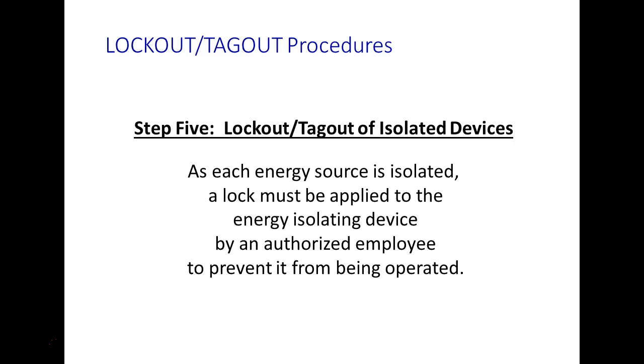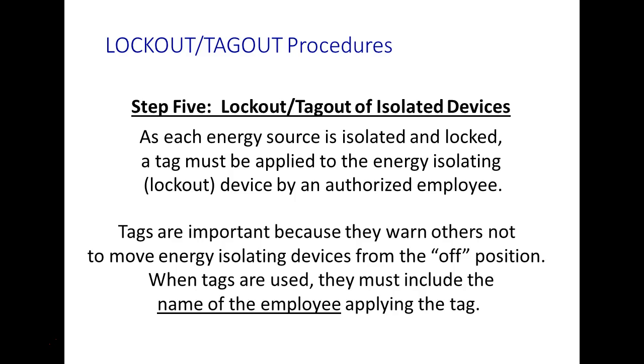And each energy source is isolated. As each energy source is isolated, a lock must be applied to the energy isolating device by authorized employees to prevent the operation. Everybody okay? And then 6, as the energy source is isolated and locked, a tag, it didn't say might be, it says what? Must be applied to the energy isolating device by the authorized employee. Let's say employers. Tags are important because they warn others not to move the energy isolating devices from the off position. When tags are used, they must include the name of the employee applying the tag. Are we okay?